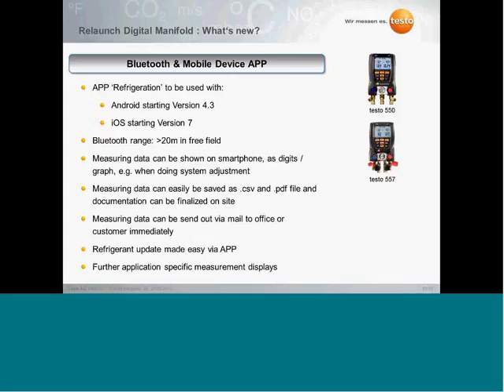The range of this Bluetooth, of this wireless connectivity, is about 20 meters in free field. So this gives you the possibility to work with your instrument, for example, at a system and walk around the system. You don't have to stand in front of the instrument all the time if you are, for example, making changes on the system and checking how these changes influence your measured data. This means you can show data as digits or as graphs when doing adjustments. We also have the possibility to send out data as CSV, that means an Excel file, and as a PDF file, for example, to the office or to a customer.